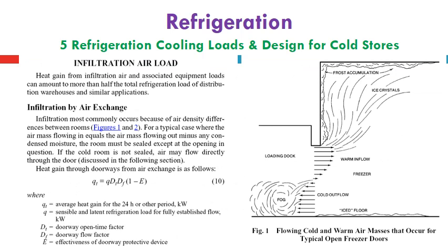This slide will discuss the infiltration air load, which is the fourth component of internal loads from outside to inside, as can be seen in figure 1, showing how the cold air can be exfiltrated from the cold store and how the warm air replacing it from the upper side enters or infiltrates the refrigerated space or the freezer due to the temperature difference and the relative density difference between the air inside the refrigerated space and the outside.